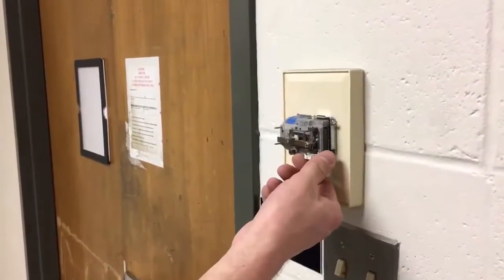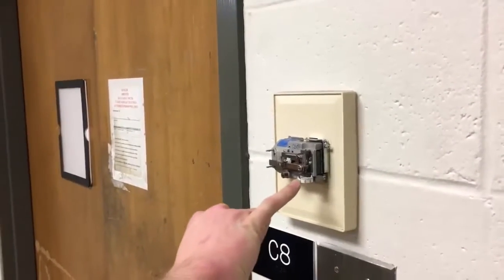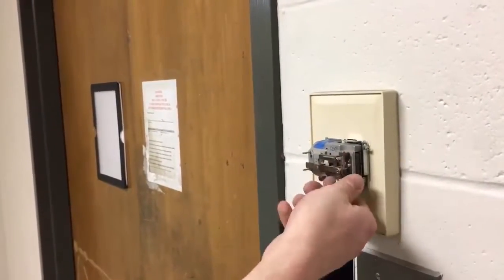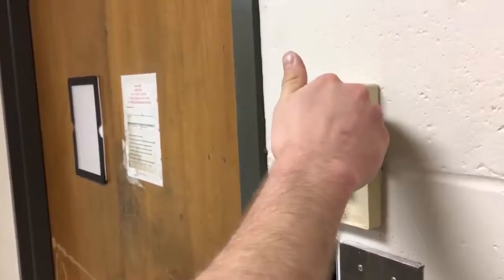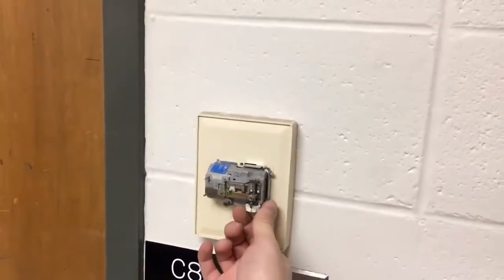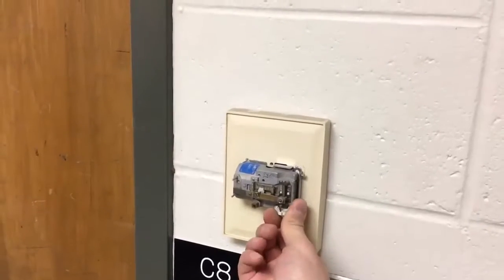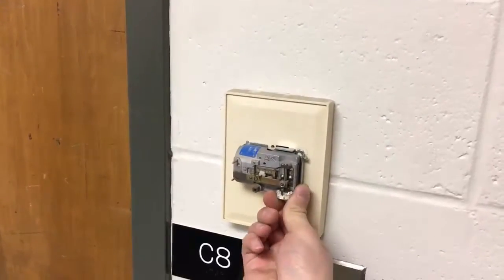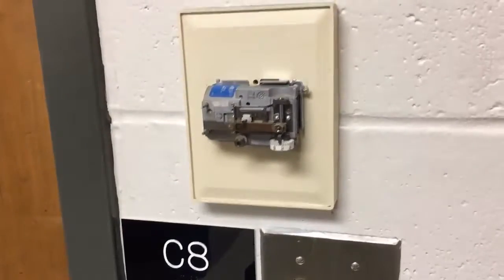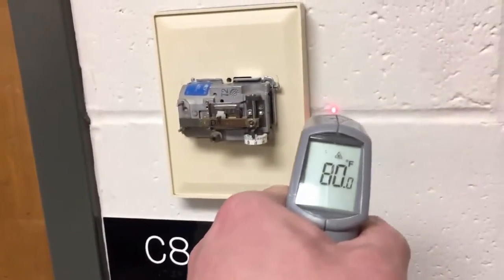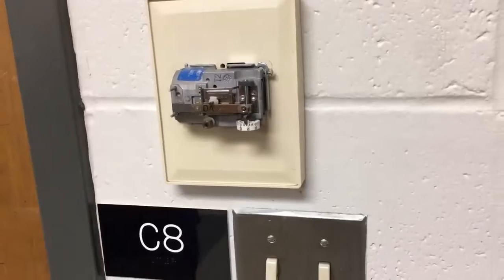To check calibration on these, I find it's usually best to start off at the lowest setting, so that's calling for pressure at the stat. That way you can listen for any leaks first. As you start to turn this dial, what you want to listen for is when it relieves that pressure. If you use your infrared and shoot next to the stat, it's 80 degrees and it thinks it's 10 degrees cooler.